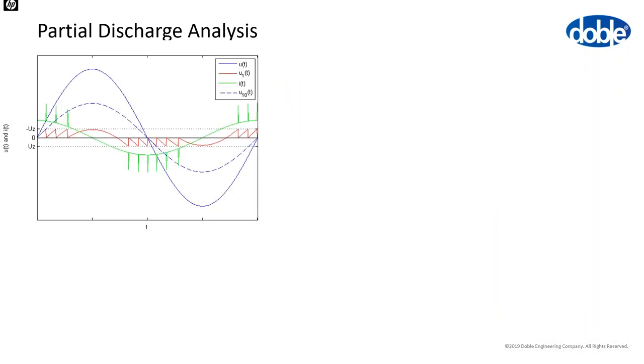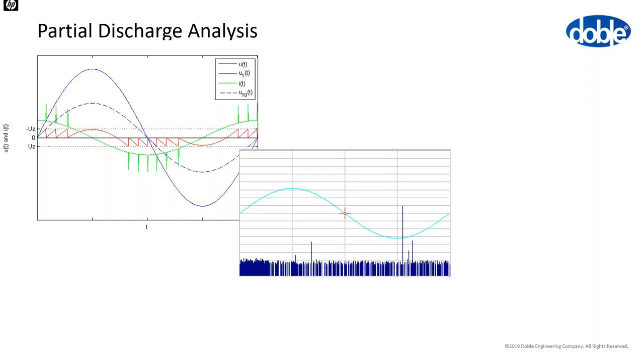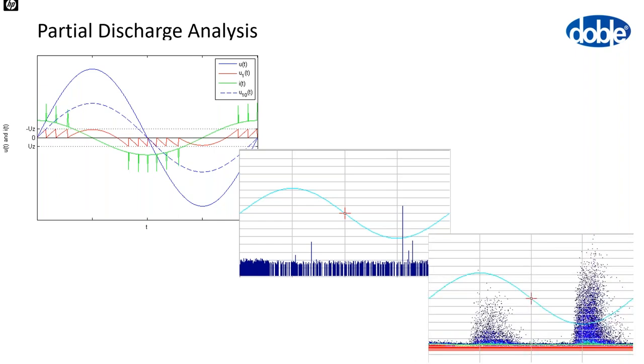How do we translate this into a plot? One cycle may show a number of discharge events. As we overlay multiple cycles onto one graph, we get a plot showing the noise floor at the bottom — very high frequency of repetition — with discharge events above it, less frequent. Certain patterns correspond to certain defect types, because specific defects produce characteristic patterns.